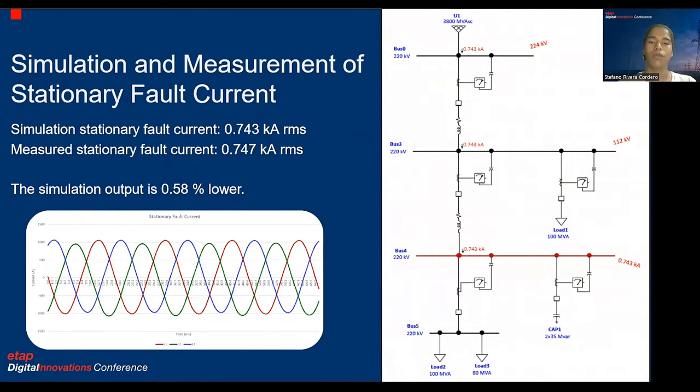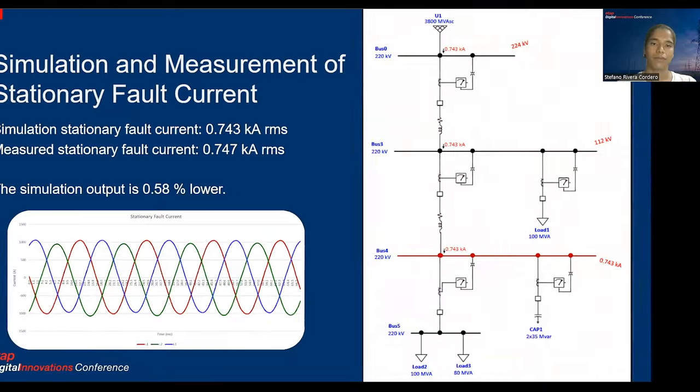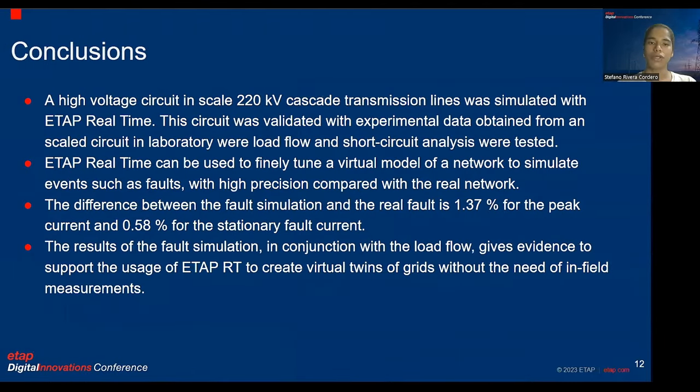In conclusion, a high voltage circuit in scale 220 kilovolt cascade transmission lines was simulated with ETAP Real-Time. This circuit was validated with experimental data obtained from a scaled circuit in laboratory, where load flow and short circuit analysis were tested. ETAP Real-Time can be used to finely tune a virtual model of a network to simulate events such as faults with high precision compared with the real network.